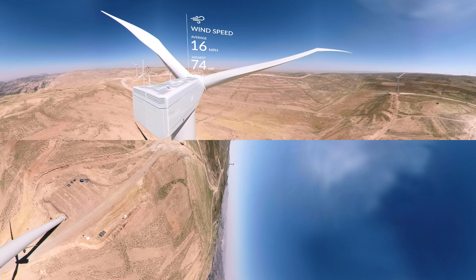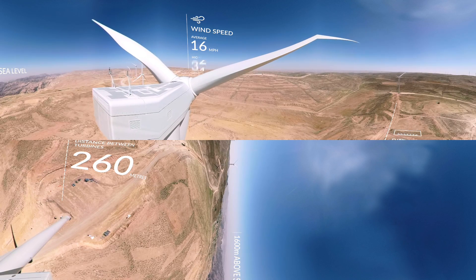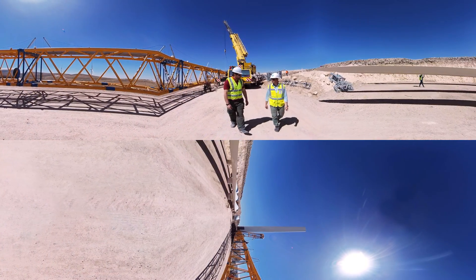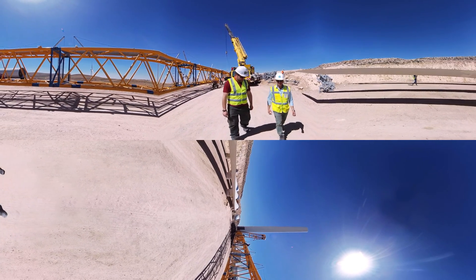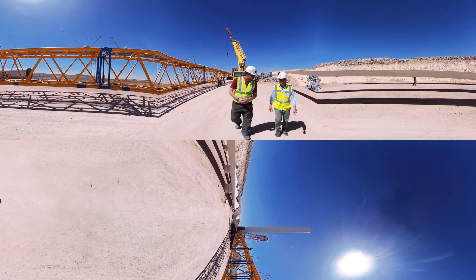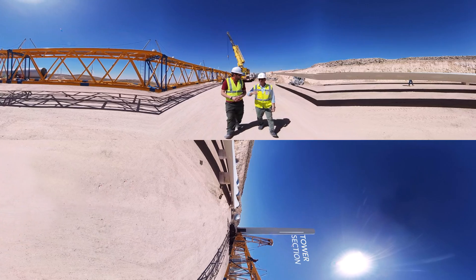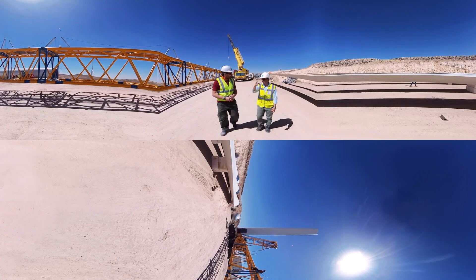This site stretches for 12 kilometers. Samir, you're one of the engineers on the site. Could you tell us how complicated it is to build a wind turbine? Once the concrete foundation is poured and the soil is backfilled to a level similar to this, we bring in a tower crane, like this one. It weighs about 650 tons. The tower crane erects the tower that makes up the tower of the turbine. It comes in three sections for our model.